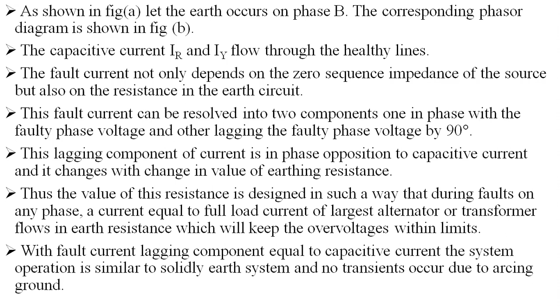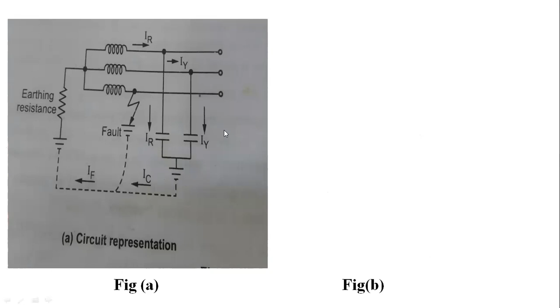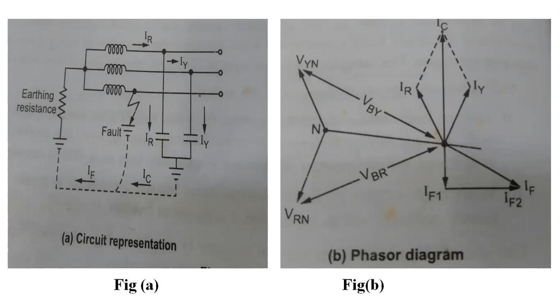With the lagging fault current component equal to the capacitive current, the system operation is similar to a solidly earthed system, and no transients occur due to arcing ground. This is the circuit representation of the resistance type, showing the earthing resistance and the fault current traveling through this ground. And this is the corresponding phasor diagram for this circuit. The fault currents IF1 and IF2 give us the resultant fault current IF. We also know how to represent our phase voltages as well as our line voltages with the help of this neutral. This is the phasor diagram.